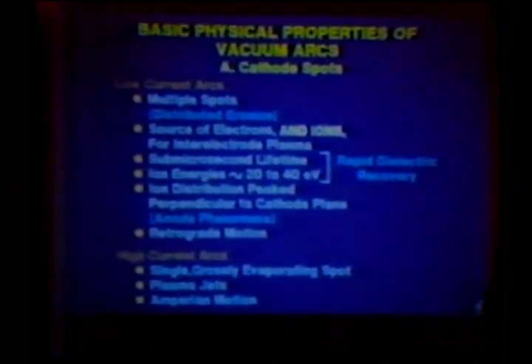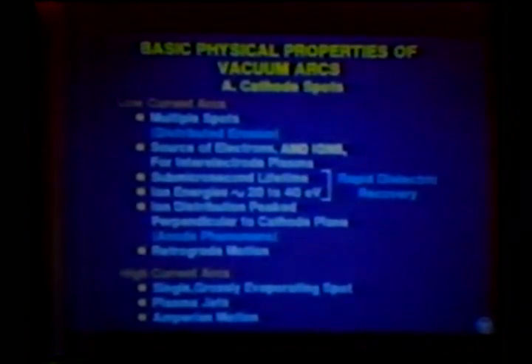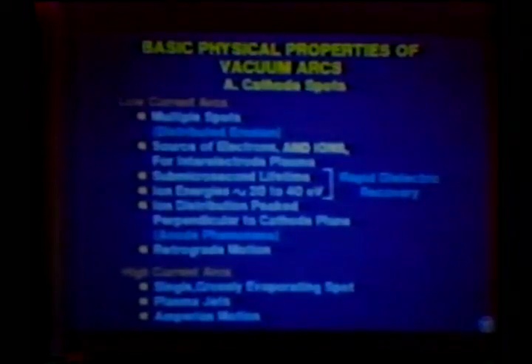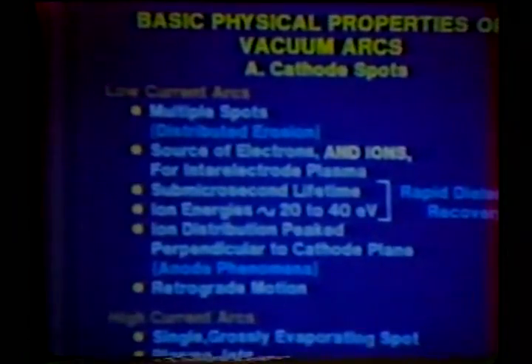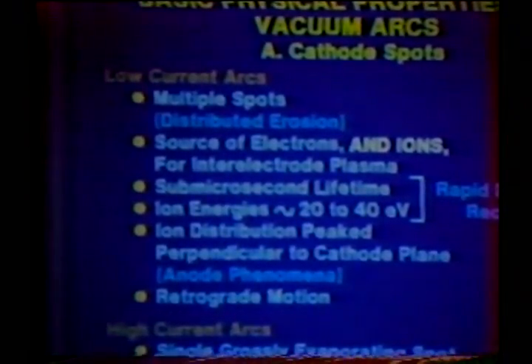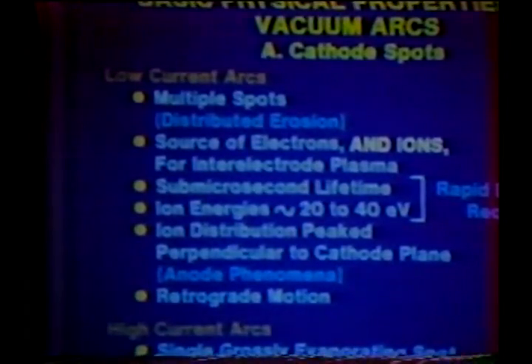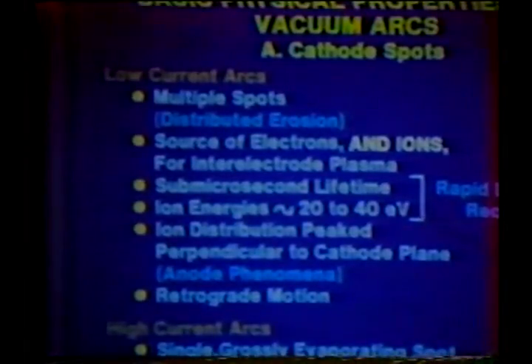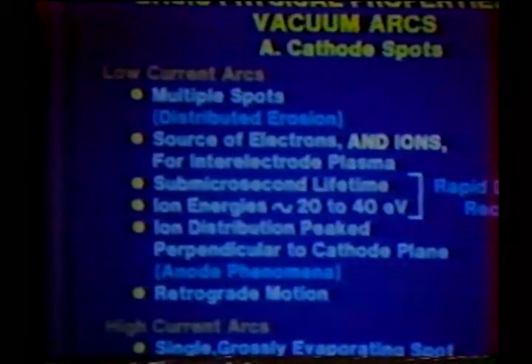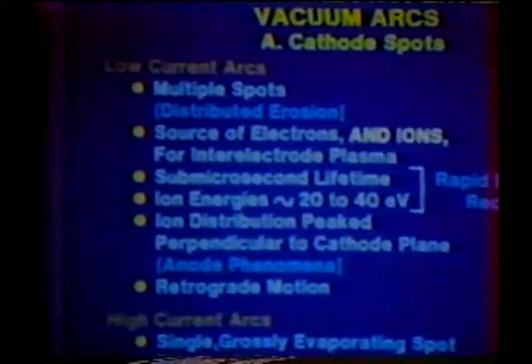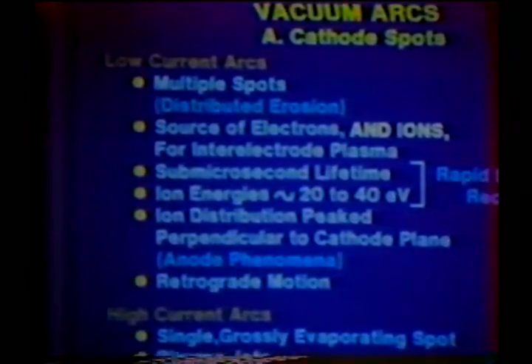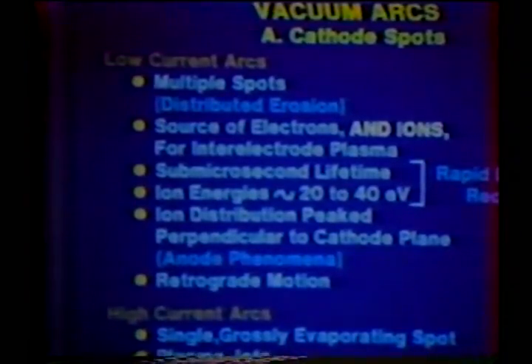In low current arcs we have multiple cathode spots, which is an attractive feature for a vacuum interrupter because you get distributed erosion. Those spots are the source not only of electrons but also of ions for the inter-electrode plasma. The spots have a sub-microsecond lifetime, as discussed at length yesterday by Professor Mesyats. The ion energies moving away from these cathode spots are of the order of 20 to 40 eV. These fundamentally unstable cathode spots and their high ion energies are both factors associated with rapid dielectric recovery. This translates to an ion — or gross plasma motion — of the order of 10 to 60 km per second. The ion distribution is peaked perpendicular to the cathode plane, and cathode spots in the presence of a transverse magnetic field move in retrograde motion.